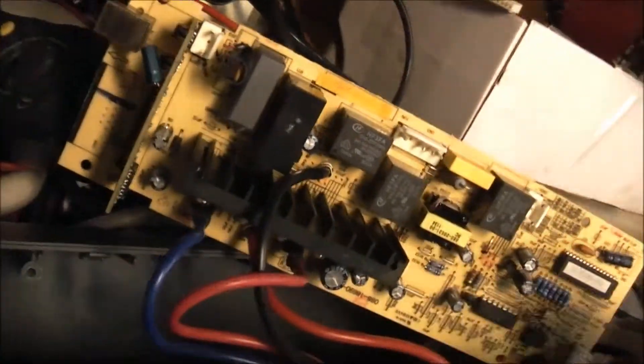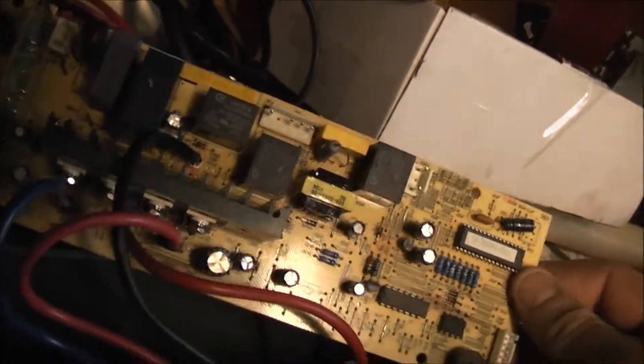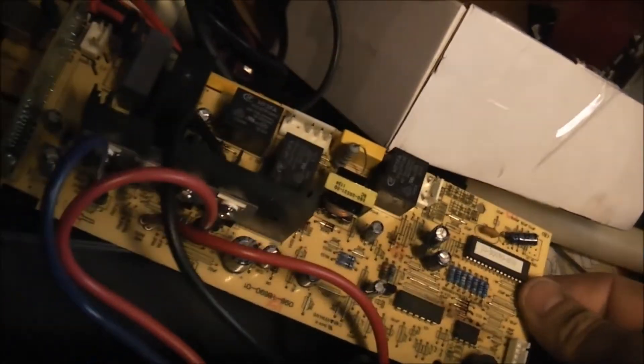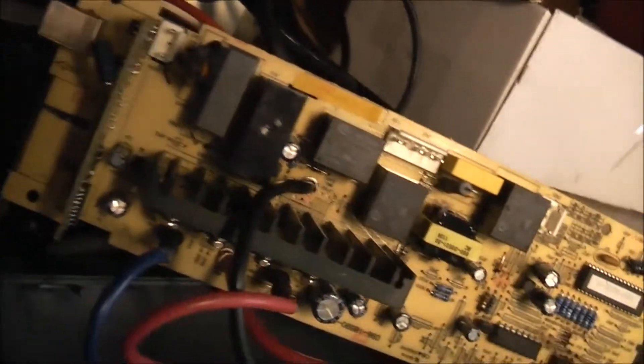It's not good for your capacitors if your battery is hot like that. There's 105 degree Celsius caps, but I keep monitoring my UPS's, so if they start getting abnormally hot, it's time to change the battery. It's a good rule of thumb.